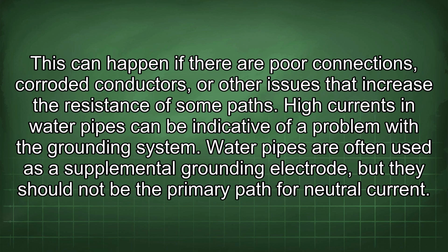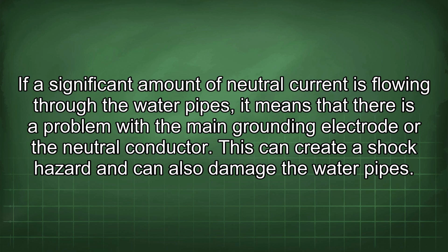Water pipes are often used as a supplemental grounding electrode, but they should not be the primary path for neutral current. If a significant amount of neutral current is flowing through the water pipes, it means that there is a problem with the main grounding electrode or the neutral conductor. This can create a shock hazard and can also damage the water pipes.